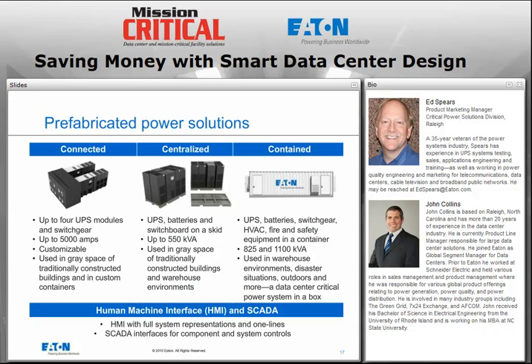Whatever you need to do, you get an entire UPS system in a package where the internal interconnection wiring has already been done. And then on the right-hand side, you see a containerized system, which we also offer, and you're probably already familiar with these types of systems. They've been around for almost a decade now. And in our particular case, we don't use these to deploy IT equipment. It's strictly for UPSs and battery, switchgear, automatic transfer switches for the generator, air conditioning to keep the cabinet cool, fire detection and suppression equipment, and monitoring and that type of stuff is all included in a power container, if you will, that we offer for larger products between 800 and 1100 kilowatts. And all these are available today, and all of these can be deployed in a catcher system like we saw.